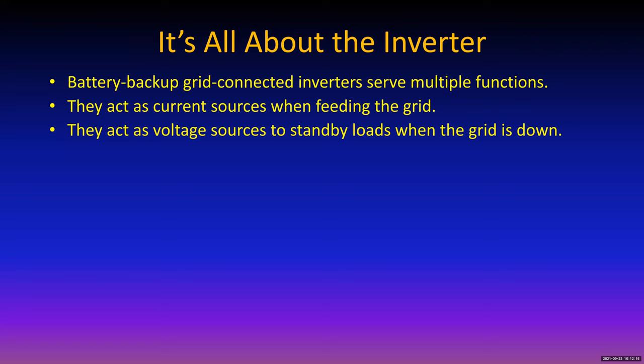If the grid goes down, then if these battery backup inverters are going to continue to serve the backup loads or the uninterruptible loads, they have to act as voltage sources, so the loads will think that the utility is still supplying them. You need to have that 60 hertz electricity—a lot of loads are dependent on the frequency being very precise.